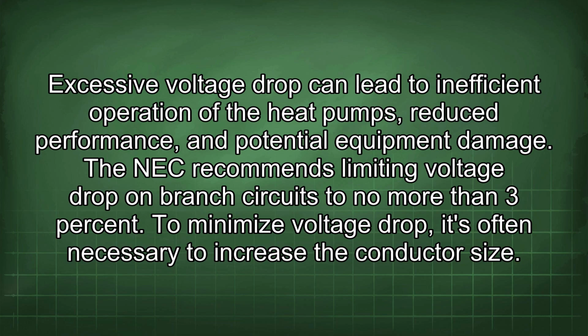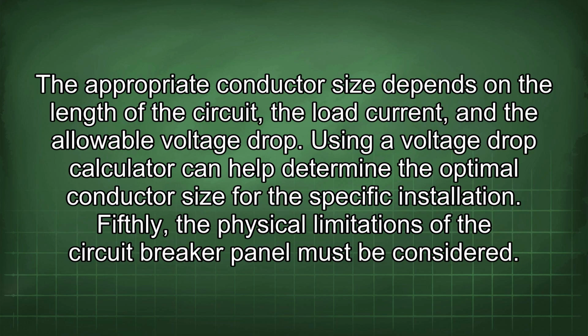To minimize voltage drop, it's often necessary to increase the conductor size. The appropriate conductor size depends on the length of the circuit, the load current, and the allowable voltage drop. Using a voltage drop calculator can help determine the optimal conductor size for the specific installation.